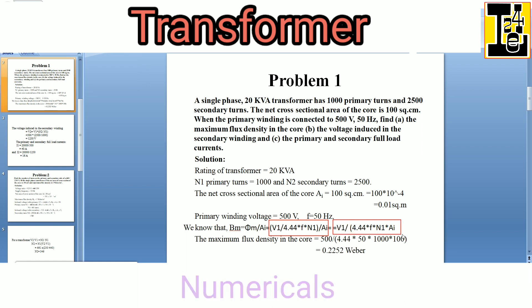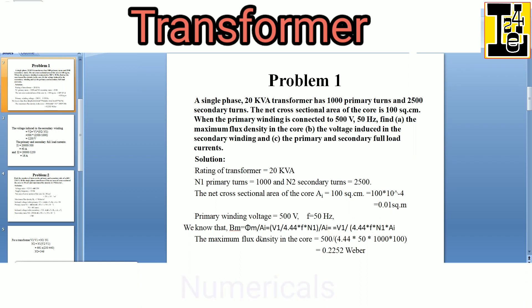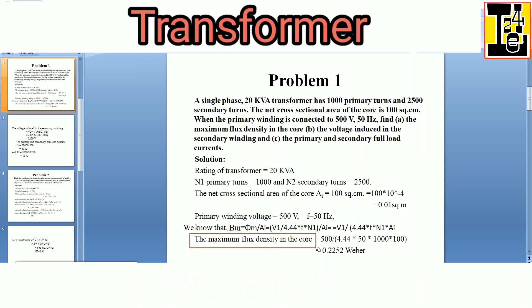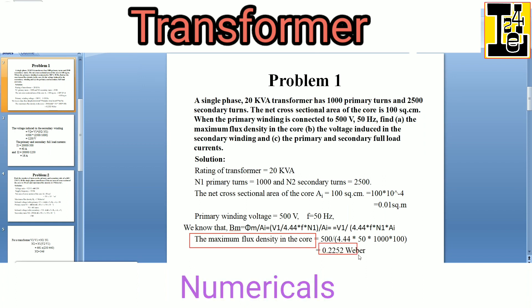Finally we get the expression as V1 divided by 4.44 into f into N1 into AI. After substituting all the given values, we get the maximum flux density in the core Bm as 0.225 Weber per meter square.